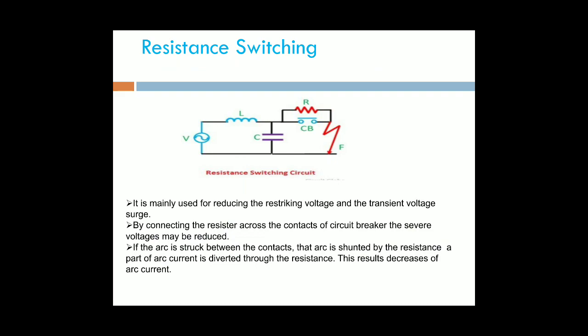Next one is the resistance switching. A fixed resistance in parallel with the contact space or arc is called resistance switching. This is the resistance, this is the circuit breaker, and this is the inductance and capacitance. When a fault is obtained, it may be short circuited. Across the capacitor, across the contacts of the circuit breaker, we are connecting one resistor.